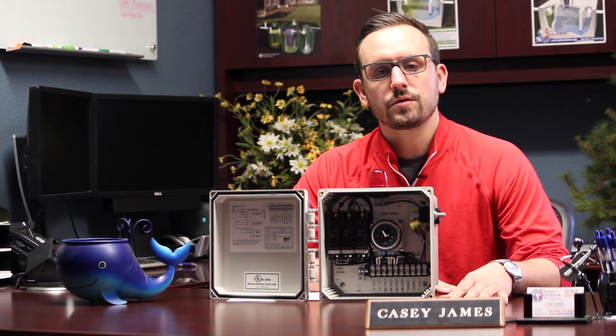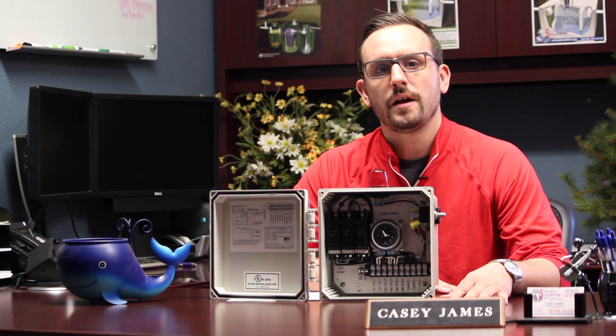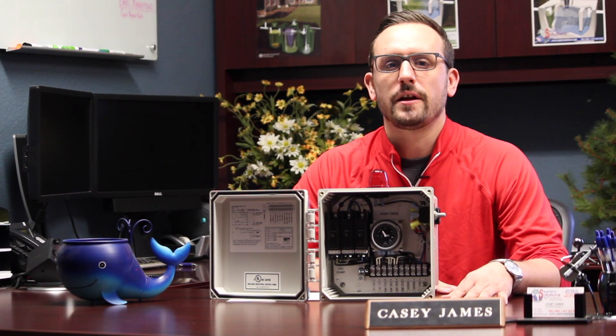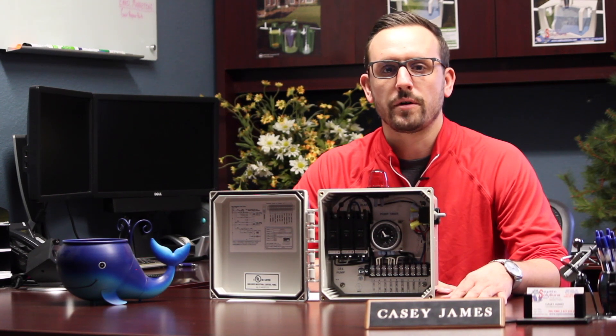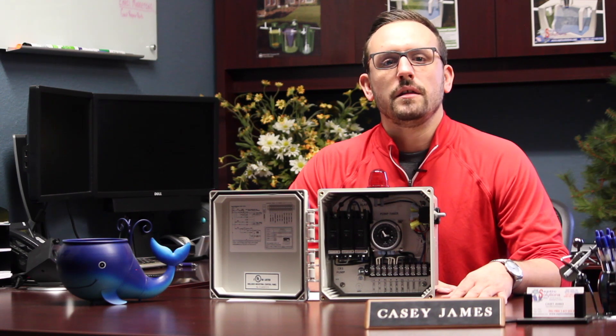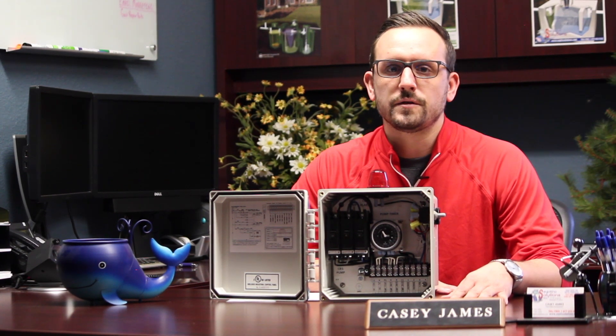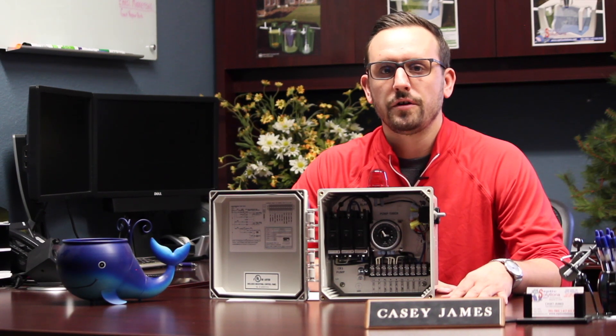The Bio-C Control Panel has three circuits: a 20 amp circuit for the submersible pump, a 10 amp circuit for the air pump, and a 10 amp circuit for the alarm and control functionality of the panel. The control panel does not have any type of air pump failure alarm, so all it simply does is power your air pump.